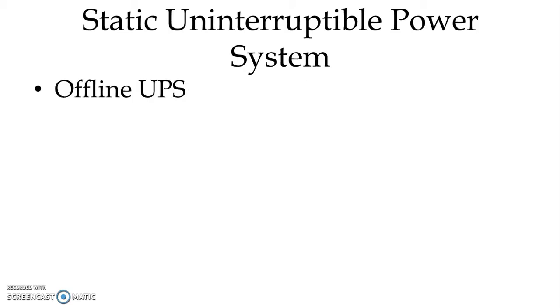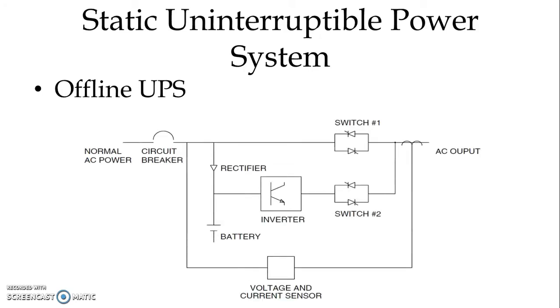We have basically two classifications in case of static uninterruptible power system, that is offline and online. Now first we see offline UPS and then we'll see online UPS, and we'll compare advantages and disadvantages of both. So in case of offline UPS, as per diagram we can see that we have battery, we have rectifier and we have inverter. We have three different major components, and we have normal AC power.